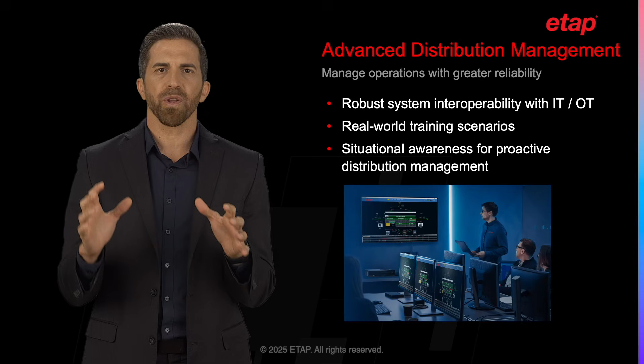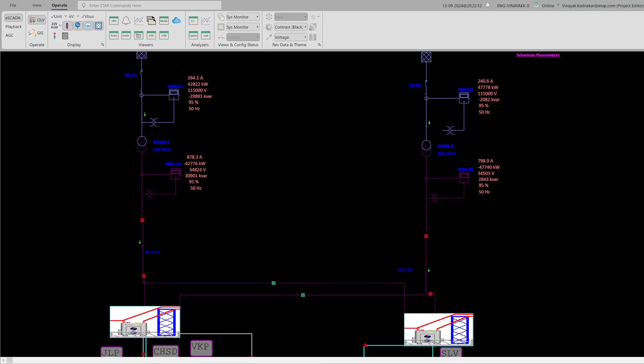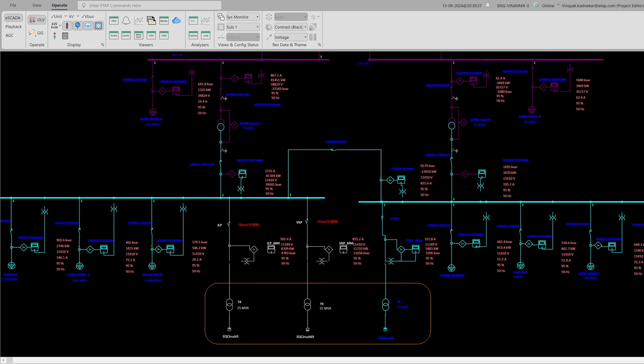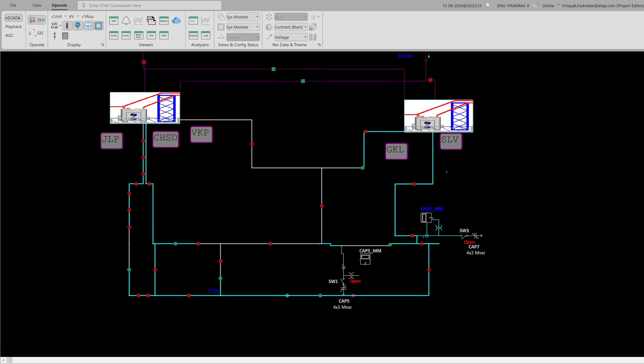Let's take a look into the different applications within ETAP. In this project, we have 115 kV, with transformers bringing it down to 34.5 kV into our distribution substation layer. We have modeled 2 substations, where power is further stepped down to 11 kV for our distribution network. We have 3 feeders, 1 de-energized and 2 energized, feeding into the distribution network. For the other substation, it's simpler, with just 2 feeders feeding into the network.